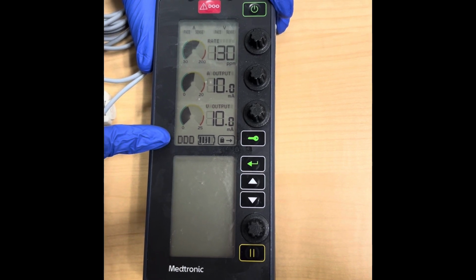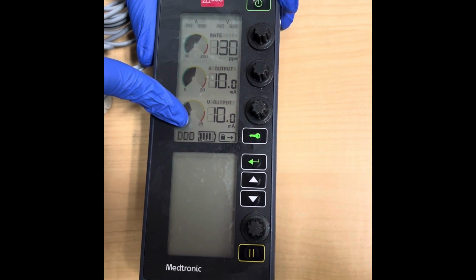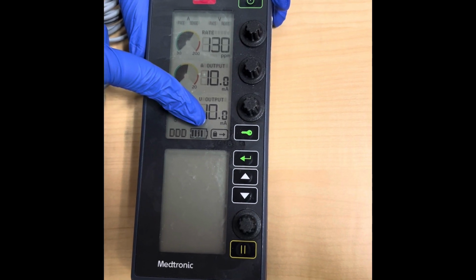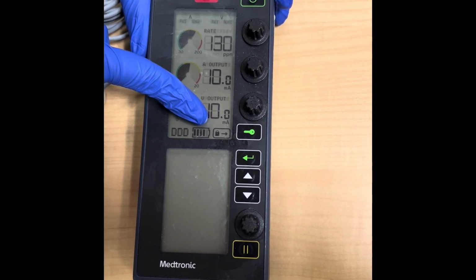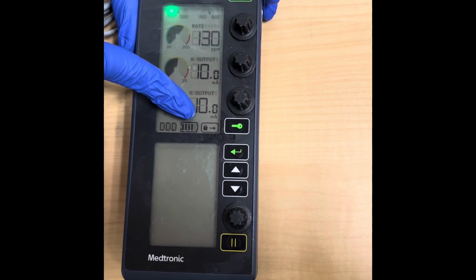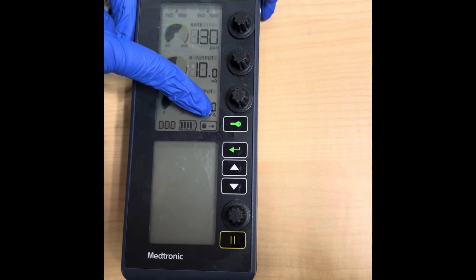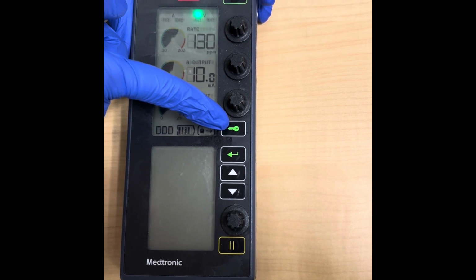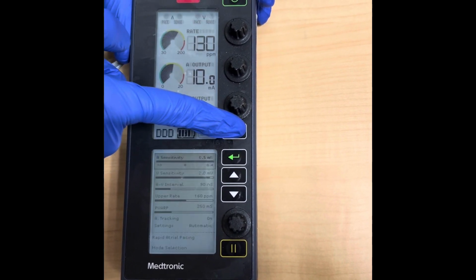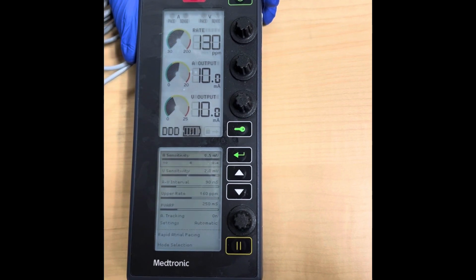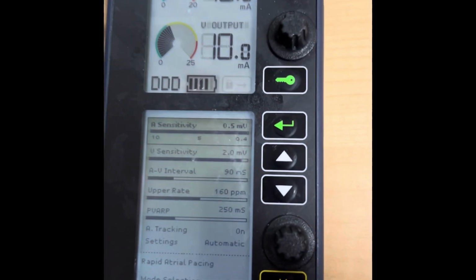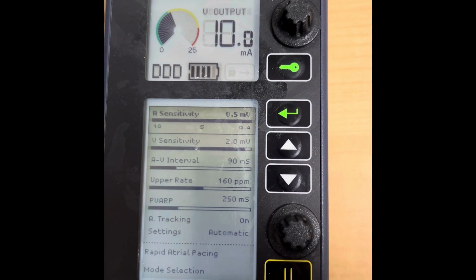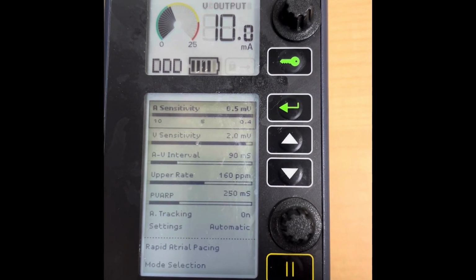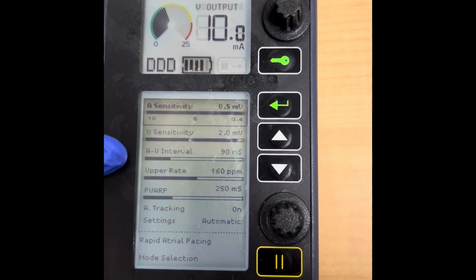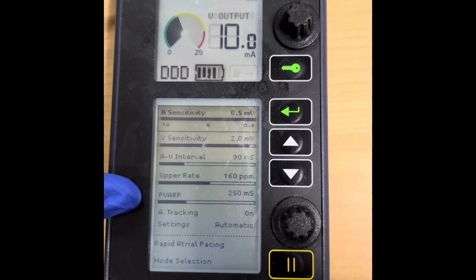At the bottom of the screen, it tells you what setting you are on. So you are currently set to pace at DDD. The next box is the life of your battery, which is important for your safety checks. And the next box is how to unlock the bottom menu. We'll demonstrate unlocking that bottom menu to get the other settings that are required for your documentation. So you're going to press the key, and then you will see the bottom menu is there. You have your atrial sensitivity, your ventricular sensitivity, your AV interval, your upper rate, and that is all that's required for your documentation.